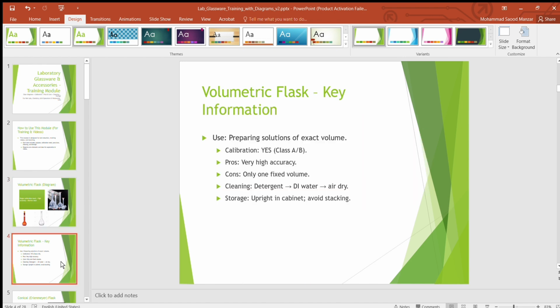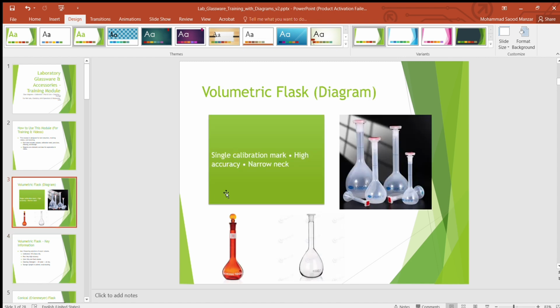Now for the volumetric flask, we need to rinse with the same solvent to remove the residue, wash with lab detergent, rinse with tap water, and do a final rinse with DI water. For oily solvents you have to rinse with acetone, then air dry or oven dry at 60 to 80. Never scrub inside volumetric glassware aggressively. Calibration: yes, it must be calibrated. It is used for exact volume preparation. A graduated cylinder, which I will cover later, is used for approximate measurement. Recommended only for research labs, QA or ISO labs.